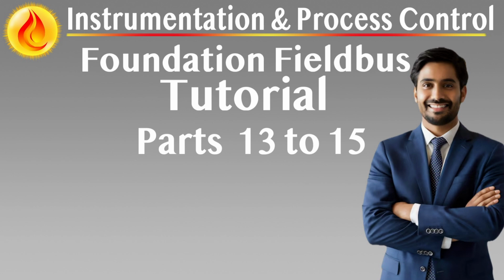Device mounting and mechanical installation must conform to process area standards, especially in hazardous locations. Devices must be installed in accordance with their Ex d, Ex i, or Ex n certifications, using approved cable glands, mounting brackets, and orientation constraints. Junction boxes should be installed within reach with labeled terminals and sufficient space for future device additions. Spur connections must be clearly labeled, secured, and protected from mechanical damage or vibration.